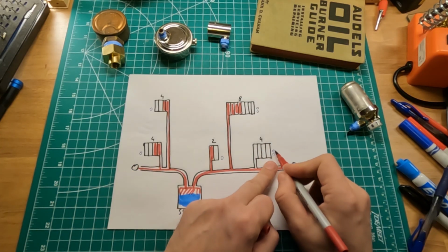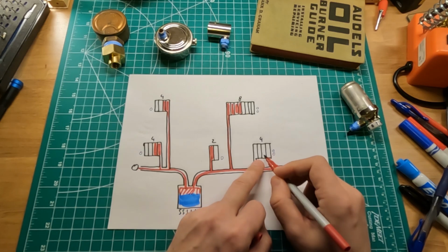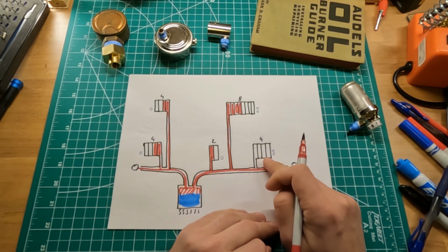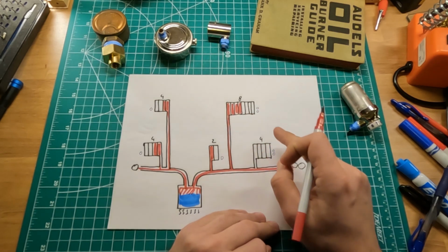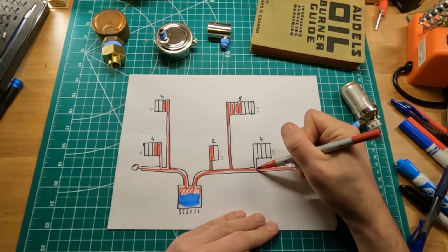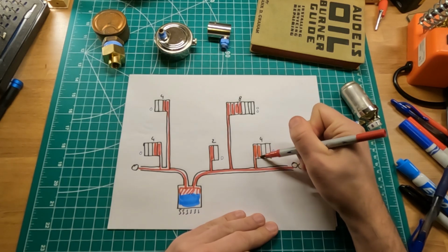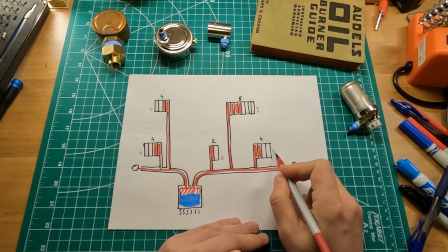So these two circles on this radiator don't necessarily mean that this radiator is going to get as hot as this radiator, which means four sections. It could be that because of the distance from the boiler, it can only heat up, let's say, only two sections, even though it has two circles for the venting, just like this one. So just be aware of it.